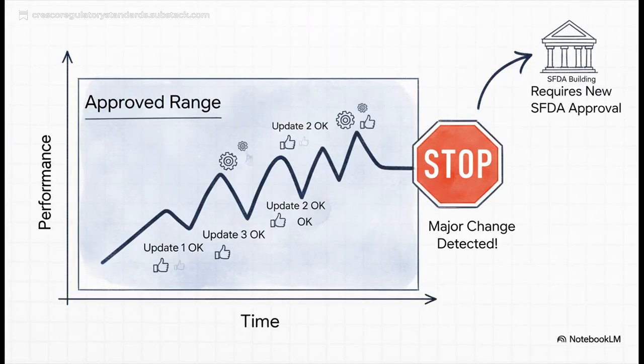And the answer comes down to what's called the performance envelope you defined way back in your original submission. Think of it like a set of boundaries. As long as the updates you make to your model keep its performance within that approved range for things like accuracy, you can manage those changes yourself. But the second an update pushes the performance beyond that approved range, bam, it becomes a major change and you're headed back to the SFDA for a new approval.